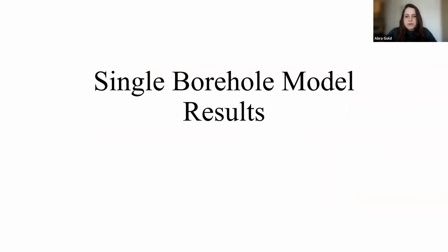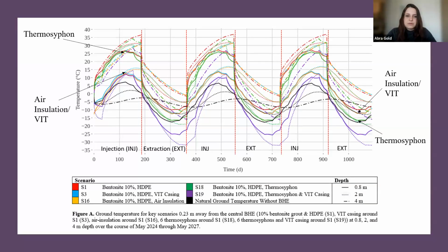And so here's our single borehole model results. What we found was that the thermosiphon wasn't as effective as air insulation or VIT in summer. And this is just a graph showing the ground temperature around the borehole about 0.23 meters away from that central borehole. And as you can see in the injection season or the summer season, when the ground temperature is the warmest, the air insulation and VIT kept the ground cooler than the thermosiphon did, but not cold enough as to reflect the natural gradient that the permafrost shows seasonally, which is demonstrated by the black curve.